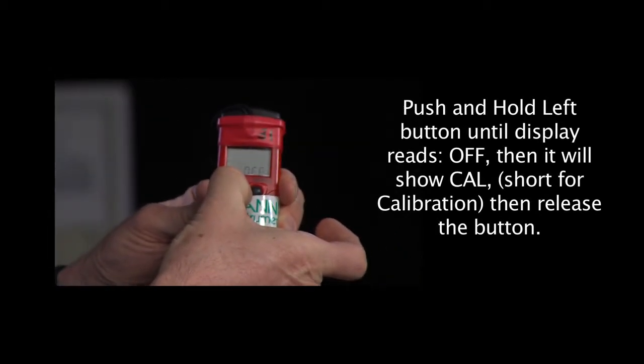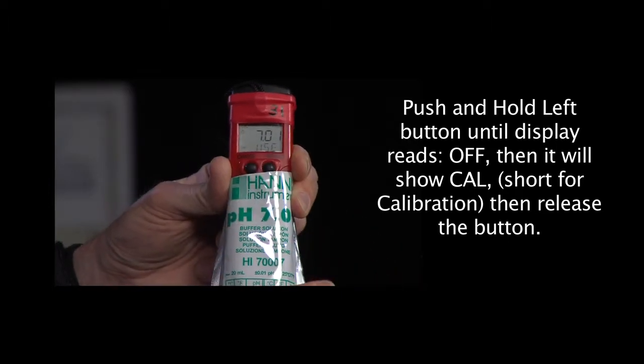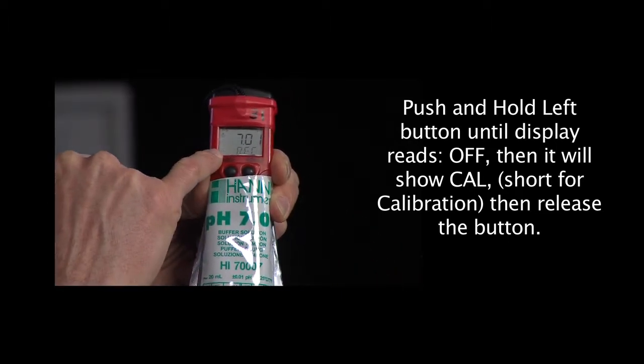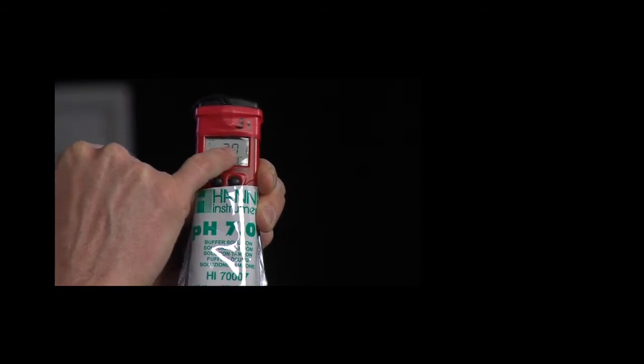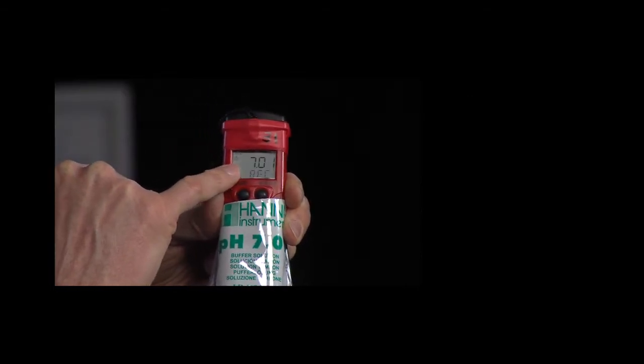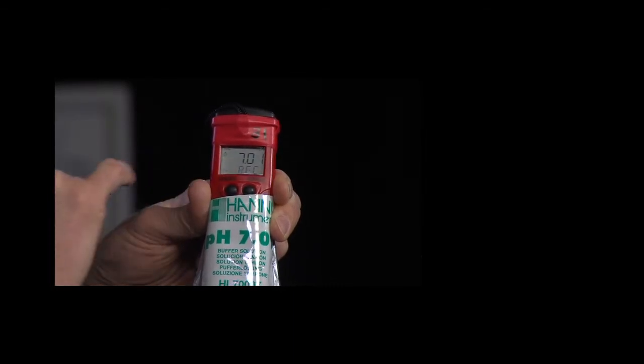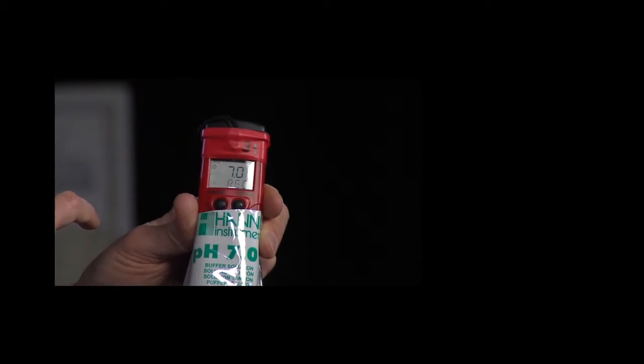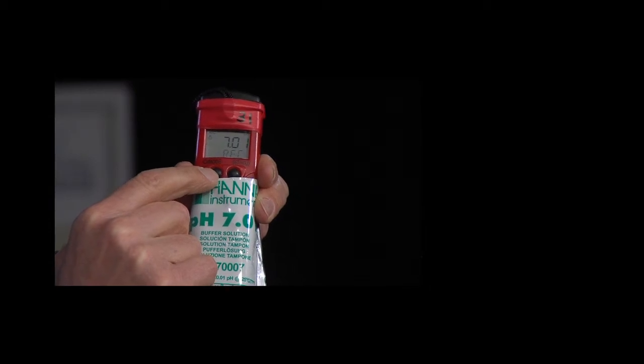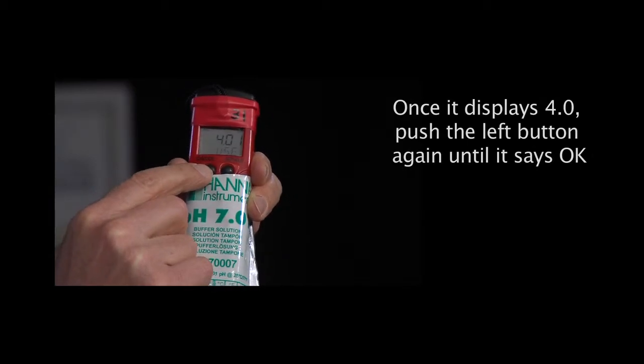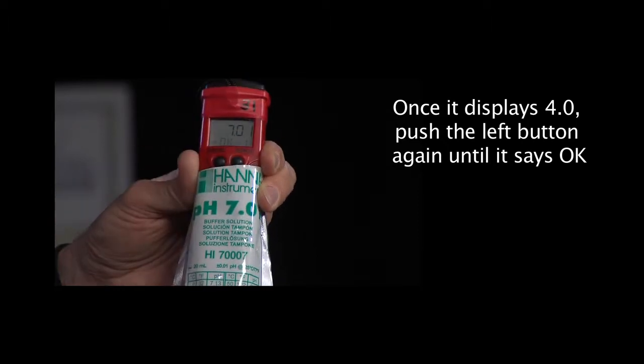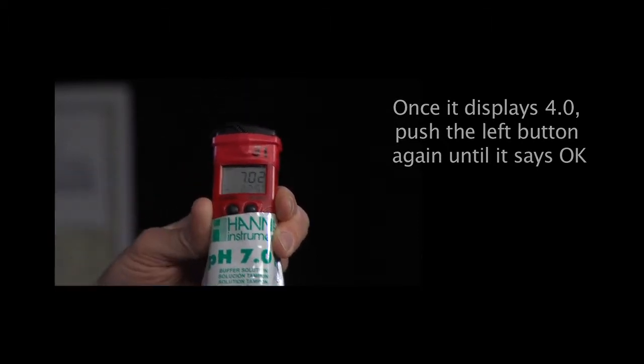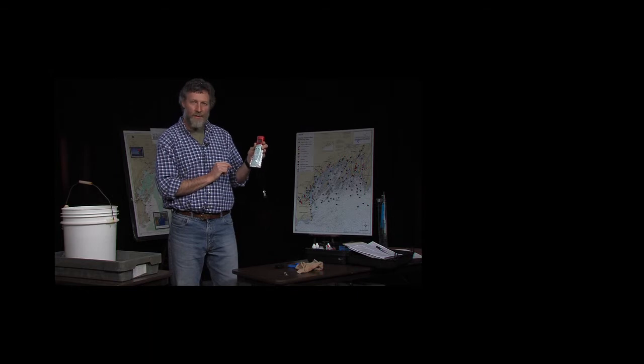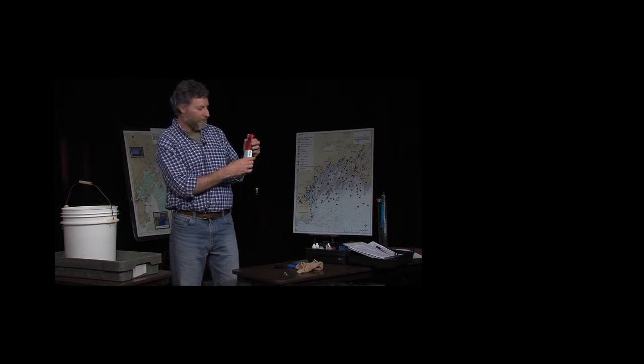So I'll just do that quickly here. We're going to hold it. It says off, and then it says cal. Take my finger off, and we'll wait for a minute. And we'll keep an eye on this number up here. It says 7. We're going to wait until that switches to a 4, which means that the meter's going to say, I want to use a 4 calibration now because I like the 7. So we'll just wait. It takes about a minute or so for it to get happy. It changes to 4. We'll push the left button once. Down at the bottom it said OK, and now we know that it's OK. It's been calibrated to this solution.